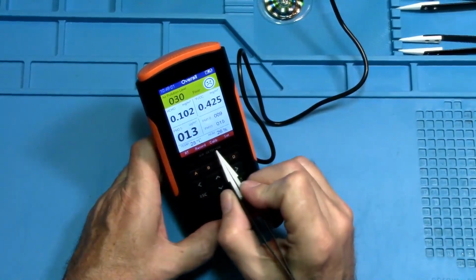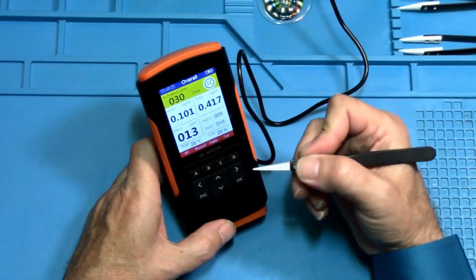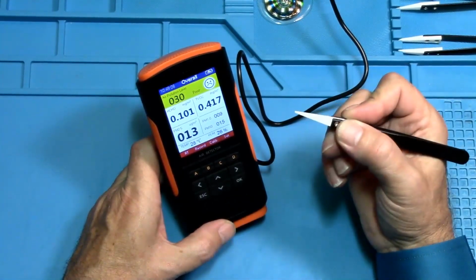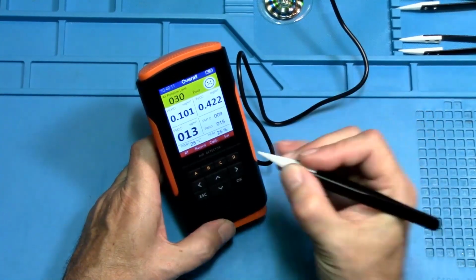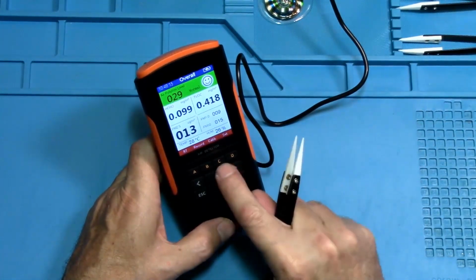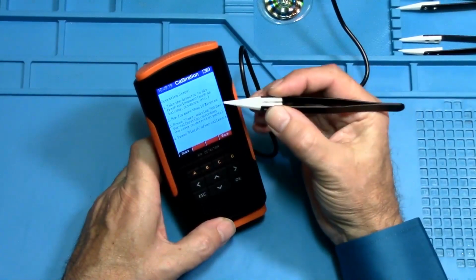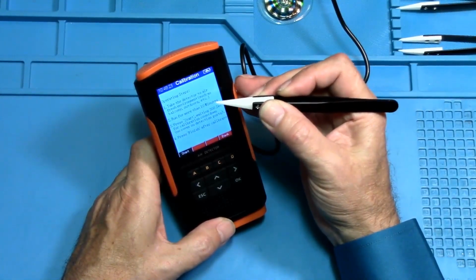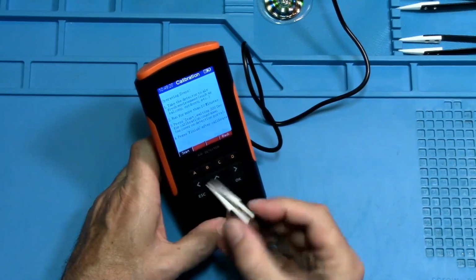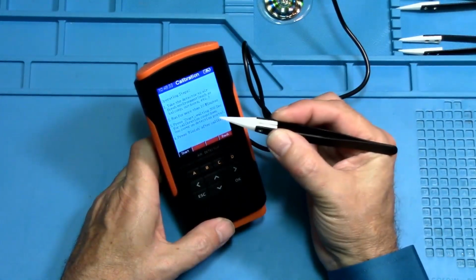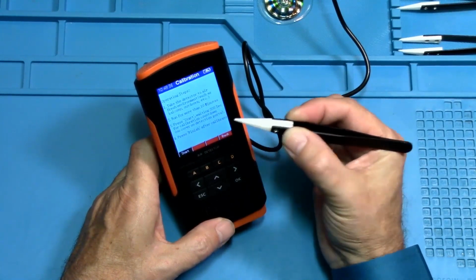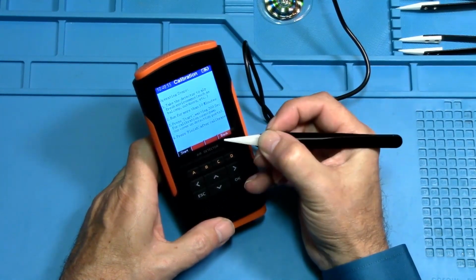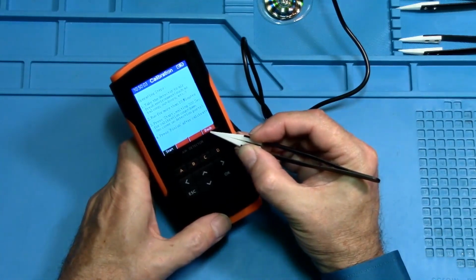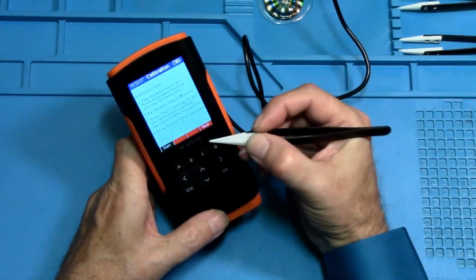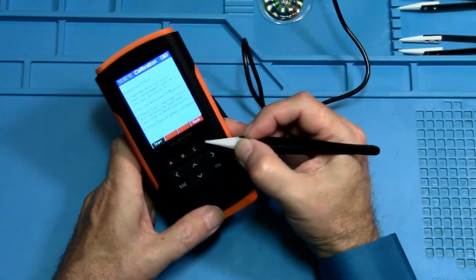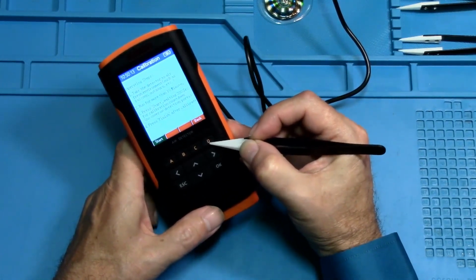To calibrate this one, do the same thing as the manual calibration, which is to take it out of the package, leave it in a fresh area for 3 or 4 or 5 hours or whatever you can do, and then go through the calibration. The calibration on this is the C button, and when you press the C button, it tells you what to do. Once you start it, which is the A button, that starts the calibration. Take it outside in fresh air and leave it for 300 seconds. And then when you come back, I believe this back here says finish after the countdown. It'll count down 300 seconds and then it'll finish. And then you press the D key right here to finish the calibration.